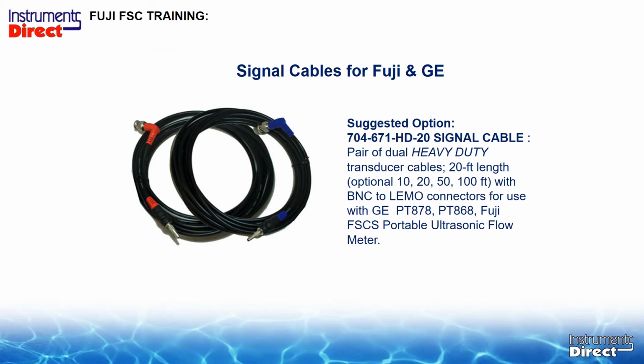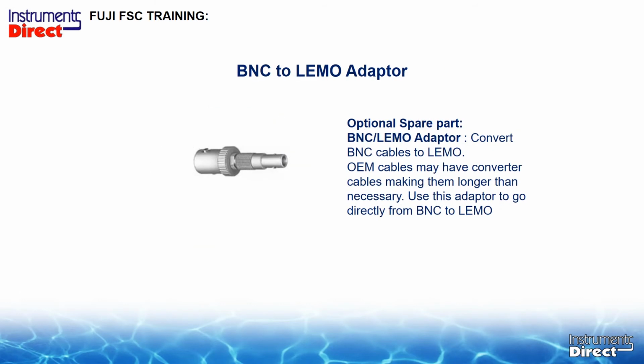Of course, after you put it on the pipe, you need to hook up the signal cables from the transducer to the electronic or handheld flow meter. The OEM cable's a little lightweight, though there are aftermarket heavy-duty cables with no junctions that go directly from LEMO to BNC, and they are available in a whole bunch of different lengths, 10, 20, 50, 100 foot, and so on. Should you have an old BNC and BNC connector, you can use a LEMO adapter. This can just go on the end of your BNC connection to make a LEMO adapter, which is the port connector on the flow meter side.